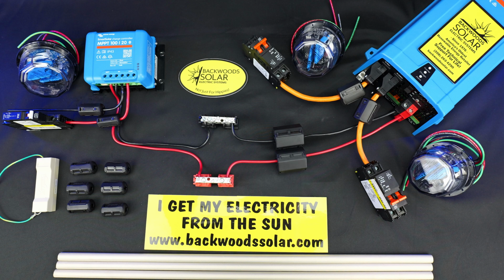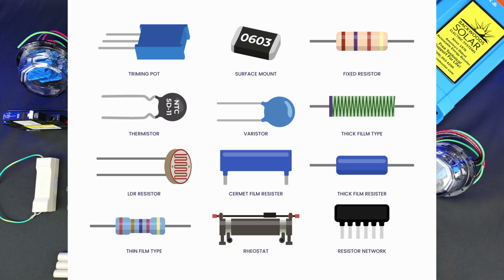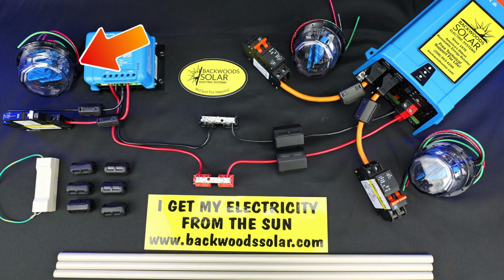Also pictured here on the screen are 3 SPDs, or surge suppression devices. These are MOV, or metal oxide varistor based SPDs. These include 1 for the solar DC input and 2 AC, 1 for the inverter input and 1 for the inverter output.